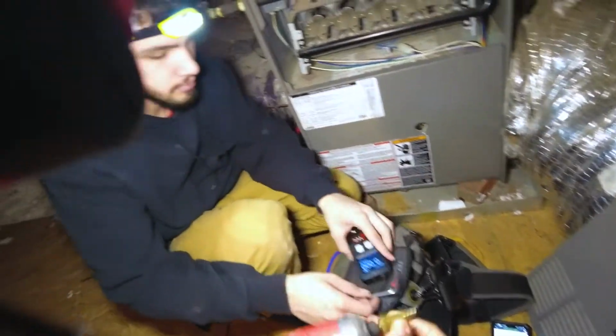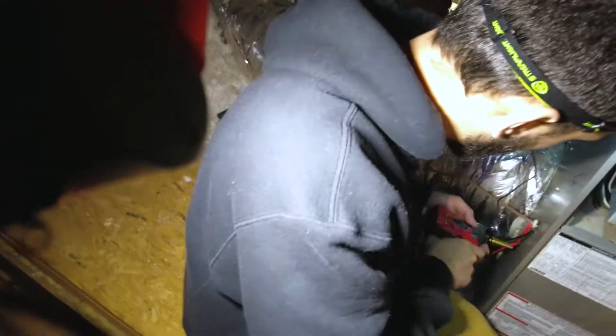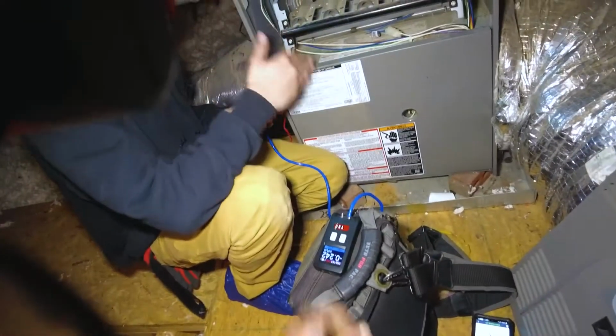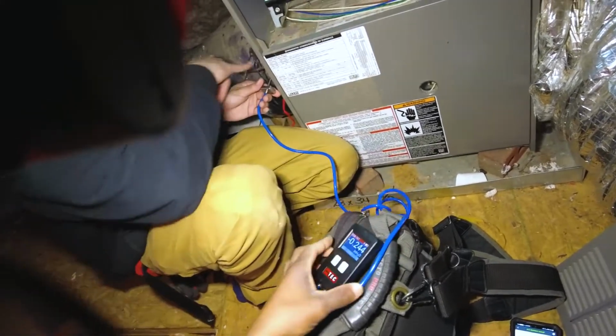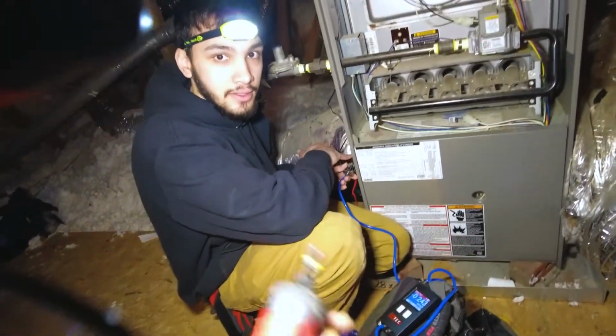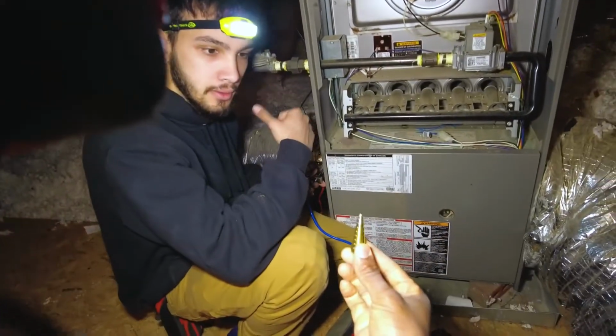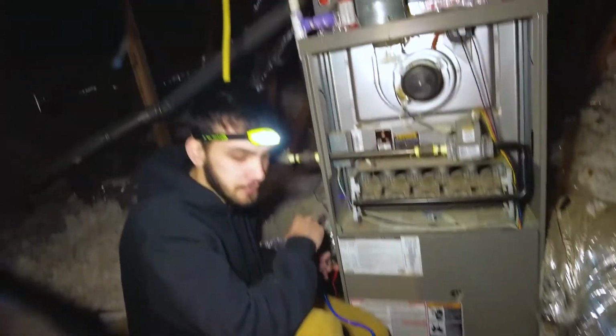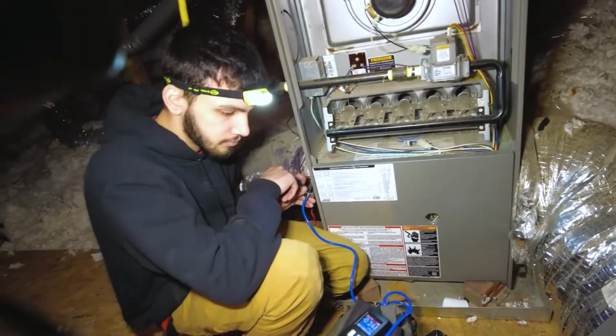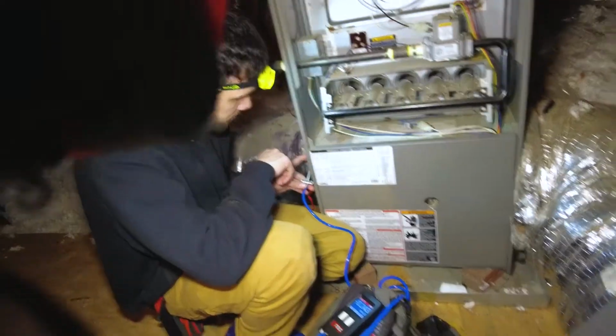Just go ahead and pop a hole into the side there. Over here? Yeah, sorry, put it through here. My apologies. So am I looking for whenever I'm trying to measure the static pressure on a manometer, I'm looking for this hole, right? Yeah, usually you will actually have to make a hole with the step bit here. As we did, you can see there's a hole over here already on the top because we're going to check the supply as well. For returns, you can usually find a hole in the returns where the lines are going in at.